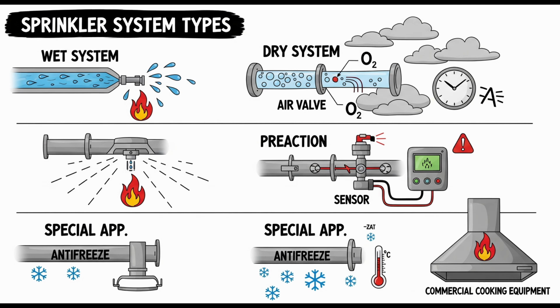Definitely. Vital maintenance info. Regarding the solutions themselves, except for one specific exception, they must be listed for use in sprinkler systems by a recognized testing laboratory. You can't just pour car antifreeze in there. Listed solutions only. What's the exception? The exception is for pre-mixed propylene glycol.